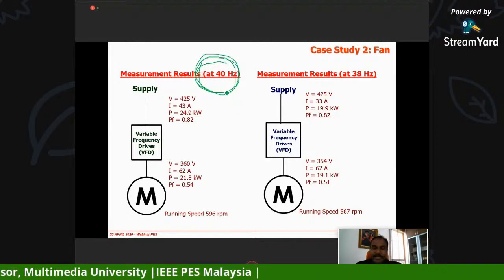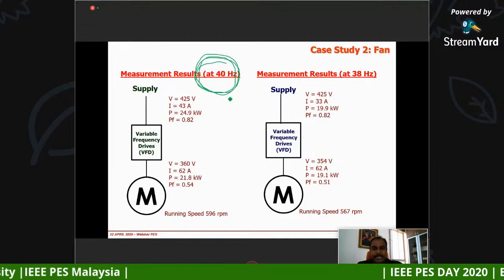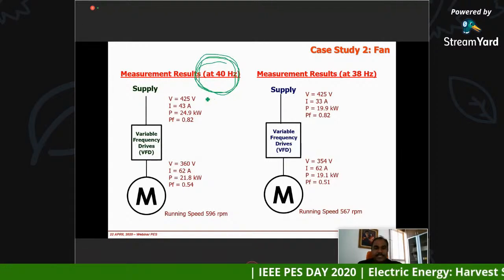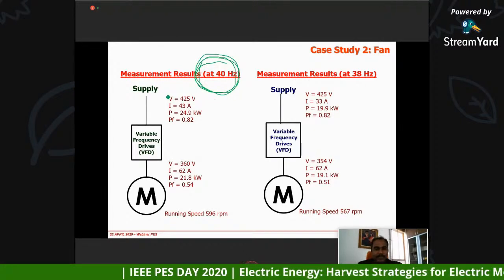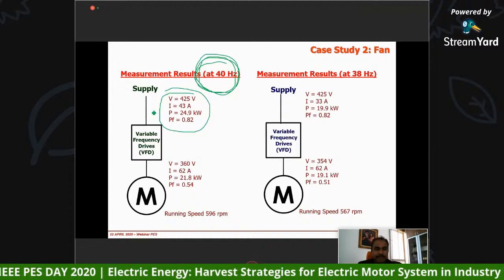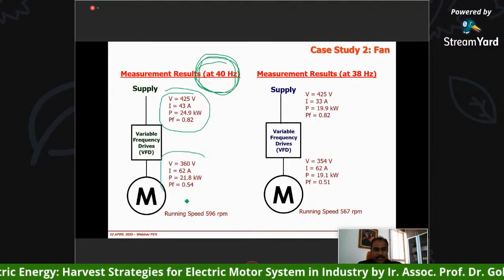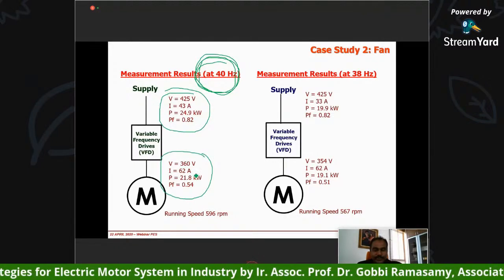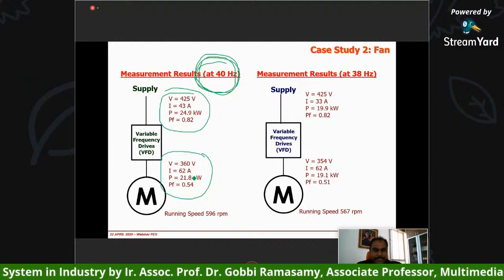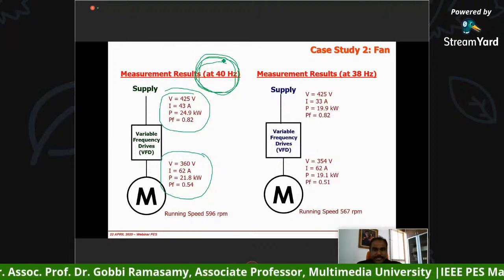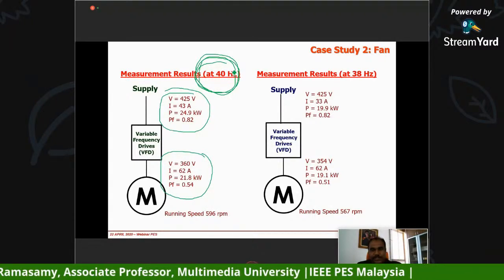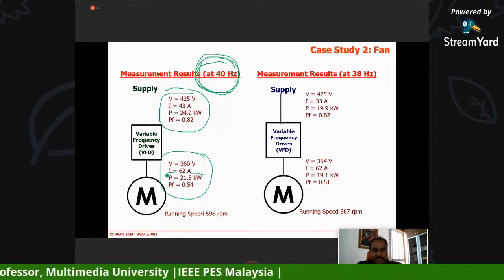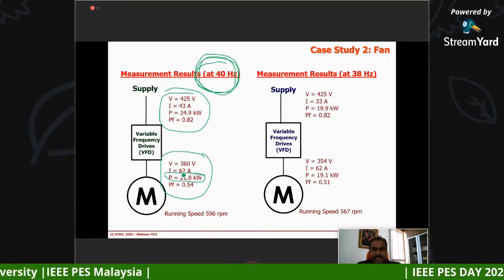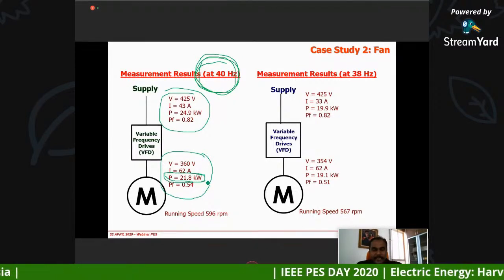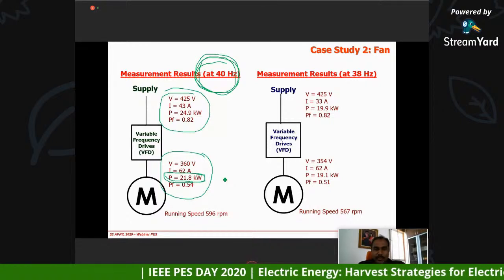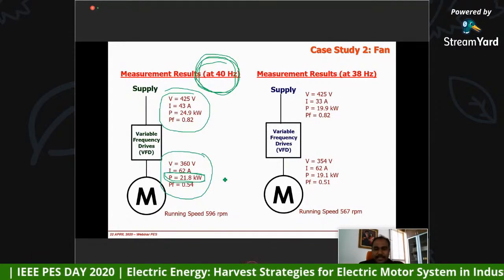So what we did was, we did some study. We said, okay, let's do a study. We hooked up our power measurement meter before the variable speed drive, and also after. So you will notice a few things here. Number 1, when it is running at 40 hertz, in fact, we tried to push to 50 hertz, we noticed the power is less than 30 kilowatt when it is running at 50 hertz. But the motor is a 120 kilowatt motor.